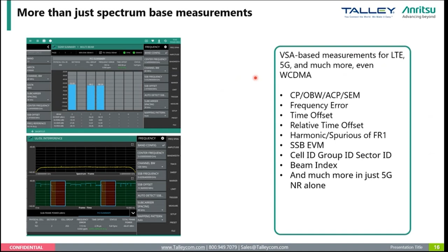Like I said before, it's more than just a spectrum analyzer. We have a lot of VSA type measurements, including LTE, 5G, and even older measurements such as WCDMA. We have quite a lot of capabilities, including frequency error offset, SSB, and EVM measurements. These are additional measurements that in the past you'd typically need a benchtop or a PC to do, which we've now enabled to be done on the instrument itself.